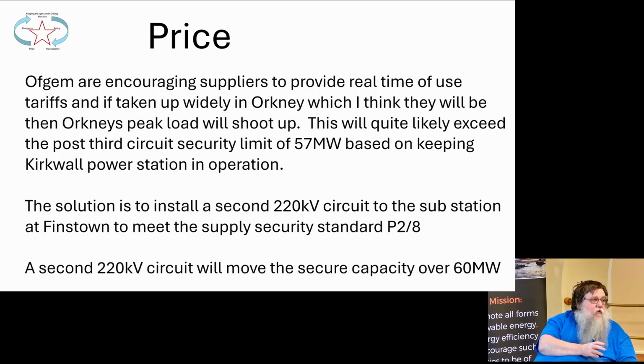And that's why I think that, when I've said around here post-third circuit, I mean the first 220 kV circuit, the security limit of 57 megawatts will be exceeded. The solution is to install a second 220 kV circuit to the substation at Finstown to meet the supply security standard P2/8. Basically, this would then put us back in the same situation as the rest of the country. We would be equal to what happens in Caithness, or what happens in East Grinstead, or whatever bit of London you fancy naming.